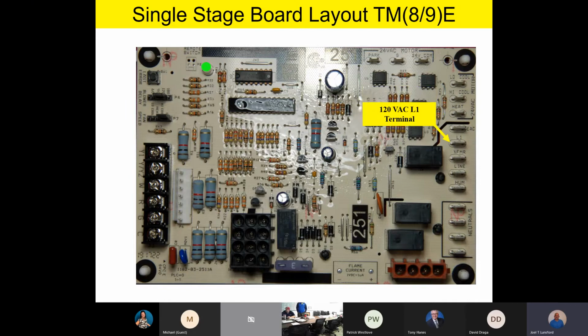As we move down the board, we have a 120 volt input, L1. This is our 120 volt input to the board that's going to run our 120 volt components. For instance, our transformer primary will be hooked into this 120 volt circuit. In addition, as we mentioned earlier, the ECM technology we're using, that high efficiency electronically commutated motor, that's what ECM means. It has power to it all the time, but it's not doing anything until we command it with a 24 volt speed command. But the power that comes into the board that powers all these 120 volt components is going to come in on that L1 terminal.